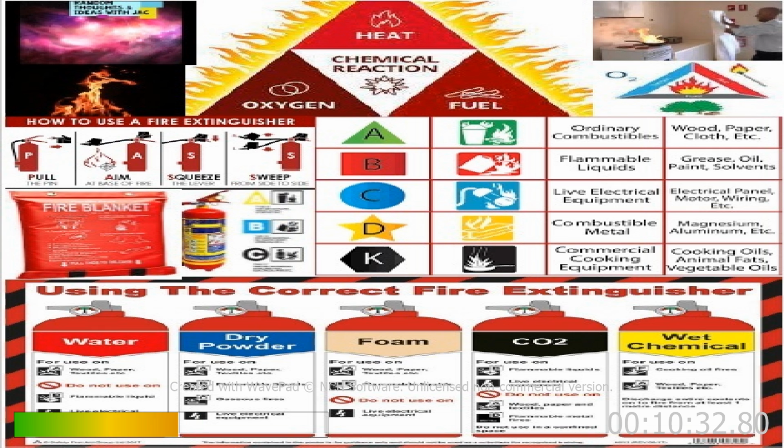A few decades ago, there was a car crash at a car racing event, and one of the metals that were burning was magnesium. Magnesium is a very volatile metal. The hotter it gets, it has these small explosions, and you can't fight a magnesium fire using normal extinguishers. But also fires involving, for instance, aluminum, any types of metals that are burning, would classify as a D or Delta class fire.